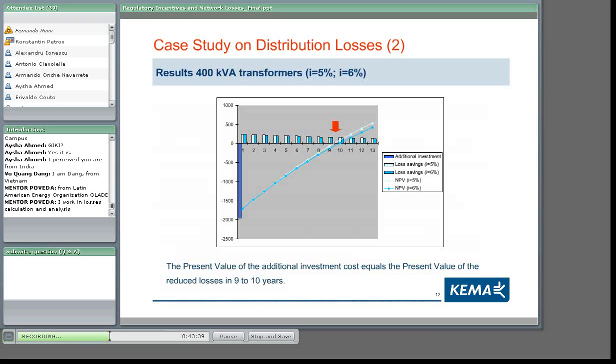In the next slides you see some selected results. The first is the result for 400 kVA transformers, with two discount rates, 5 and 6%. On the left side, the dark blue column is the incremental investment — we have to pay more to install these transformers, but we can expect future benefits. These benefits appear on the horizontal axis, continuing every year, resulting from loss savings: the gigawatt-hours saved with this equipment are monetized using the expected market price, established with the unit commitment model, roughly cost-based plus a 10% markup to account for market imperfections.